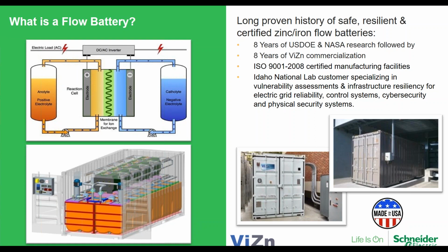That material flows - the anolyte and the catholyte - to, in this situation, 5 separate stacks of cells. Each one of those stacks of cells is about 20 kilowatts. You put 5 of them in series and you get to 100 kilowatts. That's our product. It's available in 20-foot shipping containers, and it's available in 40-foot shipping containers stacked on top of each other. It can be anywhere from 60 kilowatts to 240 kilowatts. You can line them up to create megawatts and hundreds of megawatts.